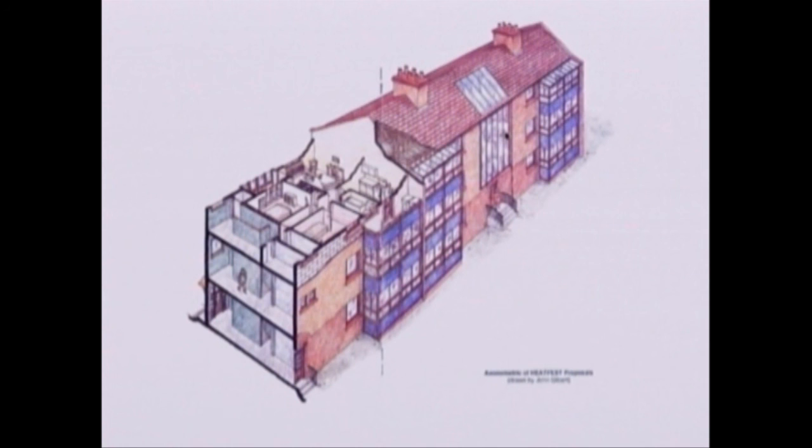Well, what were the pitfalls of what was achieved here? If we were doing it today, the first thing we wouldn't do is do the space heating as was done then. At that point in time, the tenants' prime concern was to have a full central heating system. Actually, because we were insulating to quite a high standard, we could probably have got away with a partial central heating system, but that simply wouldn't have been politically acceptable.